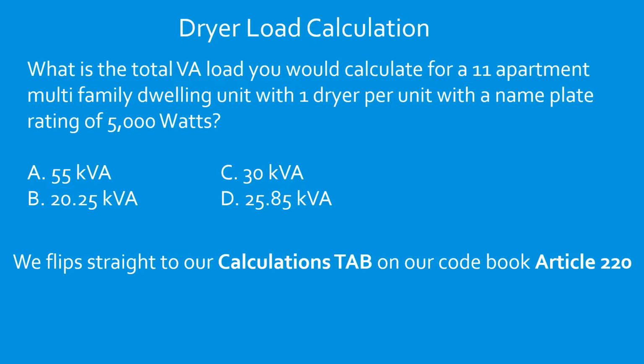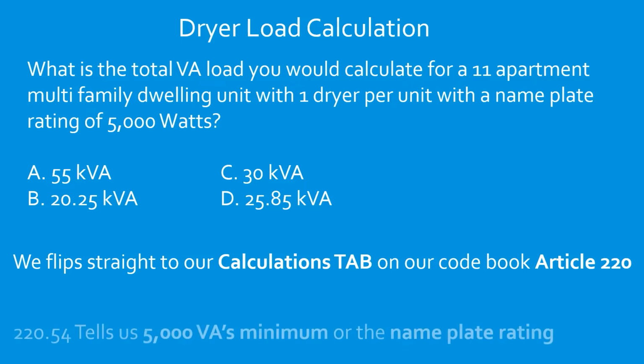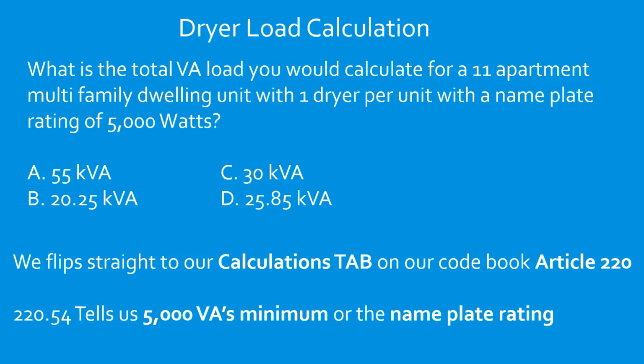So if your book was closed, or if you got this question and you were somewhere else in the book, you're going to flip straight to your calculations tab, which is going to take you to Article 220. You're going to find table 220.54 because we're dealing with dryers in the standard method. We know that it's a 5,000 minimum, or whatever the nameplate rating is, so we're good here.